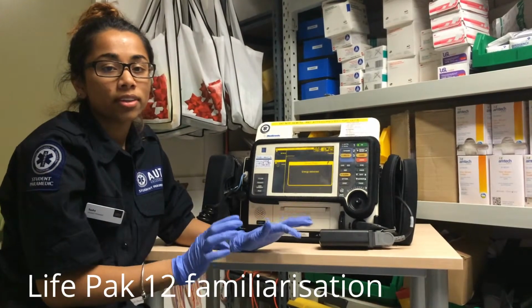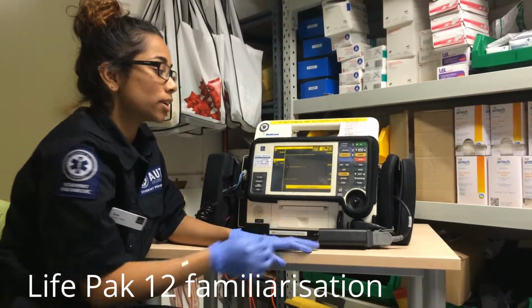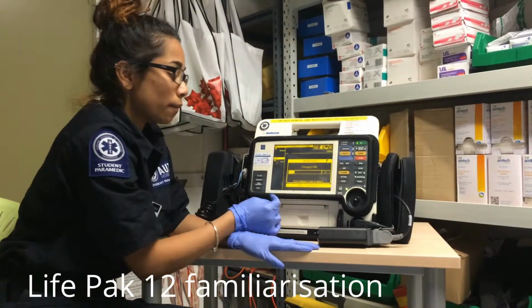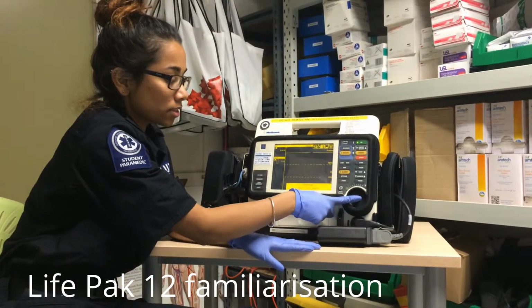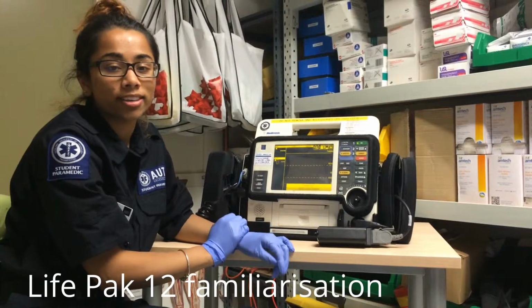So to disarm the shock is a similar technique, so you want to charge the machine once again. But to disarm it, you just click the select button like so, and it will disarm the charge.